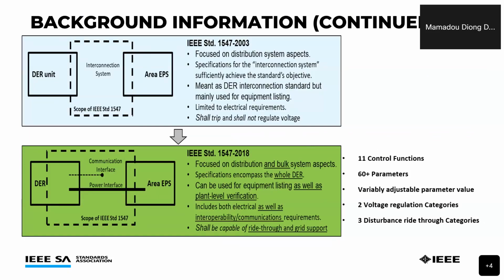1547 actually started back in 2003. At the beginning, it was mostly focused on distribution only, providing specifications for interconnection systems — everything necessary at the time to safely and reliably connect DER. Essentially, DER had to meet certain standards and be listed. But everything has some limitation. For instance, we couldn't do ride-through at the time, and we couldn't allow DER to support the grid, because we didn't have as much knowledge and experience with that standard yet.